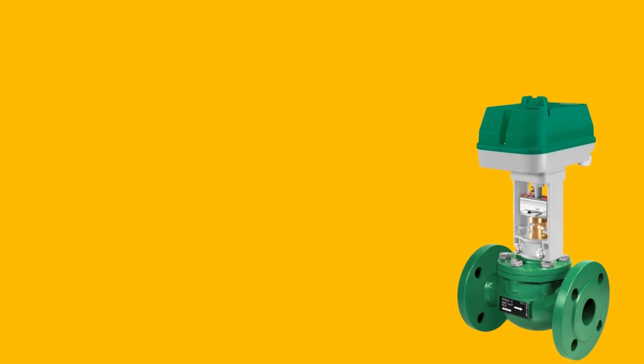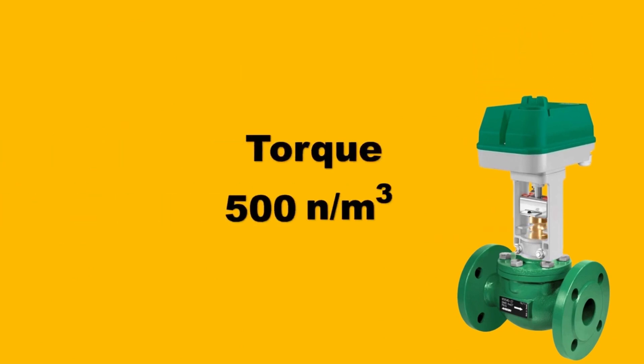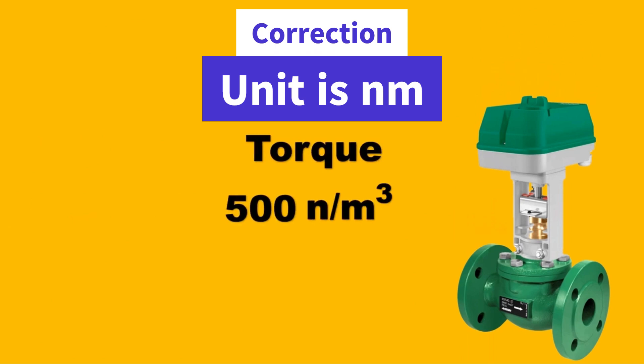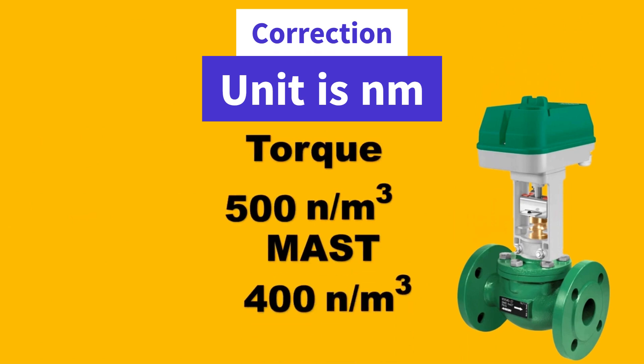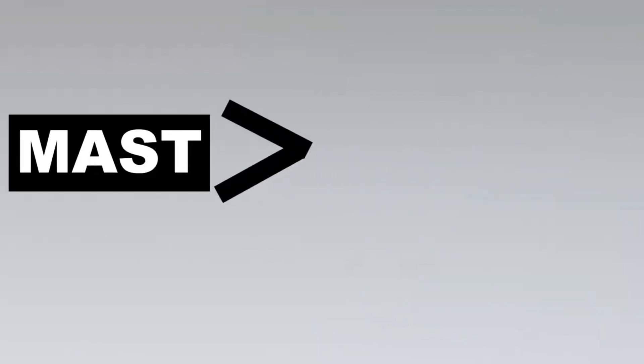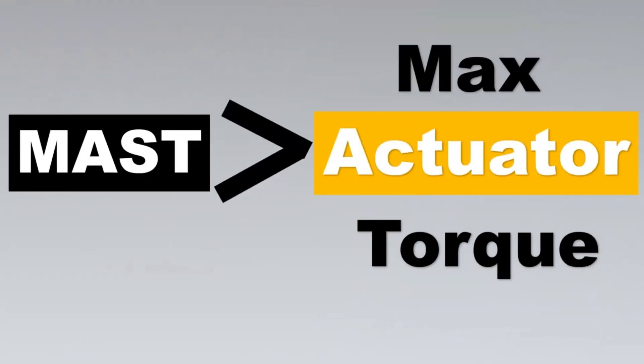Imagine we take this assembly of actuator and valve and put it all together. The actuator can have a torque of 500 Newton-meters, however the MAST is 400 Newton-meters — that is, the Maximum Allowable Stem Torque is just 400, but we can give 500. Is this combination good? The answer is no — it will destroy your valve. So we learn a very important equation: MAST must always be greater than the maximum actuator torque.